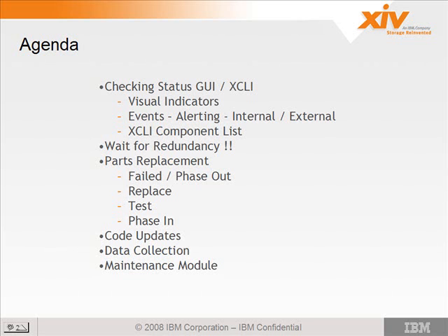There were a lot of questions on the way the data is distributed throughout the system. The reason I asked the question, particularly: a module died, rebooted, something bad happened to it. It's now being phased out, and maybe 4 hours later, phase out finishes. Then the SSR doesn't have any parts, so he does a test on it, the test passes, so he phases it in, and that takes what, 4 hours? Correct. And then 20 minutes later it reboots, so it phases out, which takes another 4 hours.